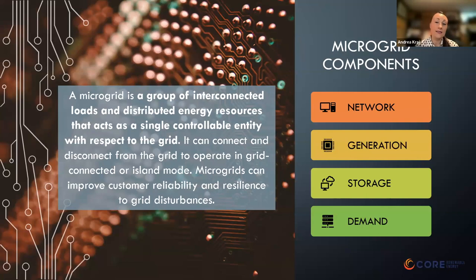So essentially what we have is demand, which is load, customer load. Then we have a way to provide that, which is our generation. And then the gaps need to be filled in with storage. Microgrid systems require storage. You can operate without it, but I wouldn't necessarily define it as a microgrid, but we'll get to that. And of course, you have everything that controls it and brings it together, which we call the network itself or the grid. Advanced microgrids enable local power generation assets, including traditional generators, renewables, and storage, to keep the local grid running, even when there are larger grid disturbances or interruptions, and in remote areas where there's no connection to a larger grid. This is called islanding. If there is no connection to that larger grid, you would be an islanded microgrid.